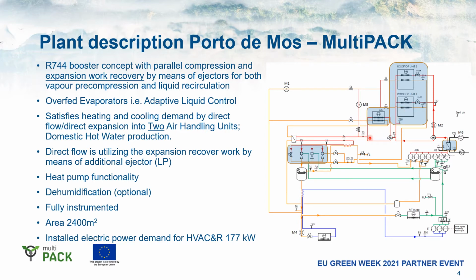The entire pack, as you see, is fully instrumented with mass flow meters and temperature and pressure sensors. So there's a dedicated measurement system which we utilize for the MultiPACK system, beside, of course, the Danfoss controllers, which are controlling and monitoring the system as such. So we have access to both these measurement devices and control devices, so we can compare different measurements. The shop has an area in the order of 2,400 square meters, and the complete installed electric power demand for the pack is about 177 kilowatts.